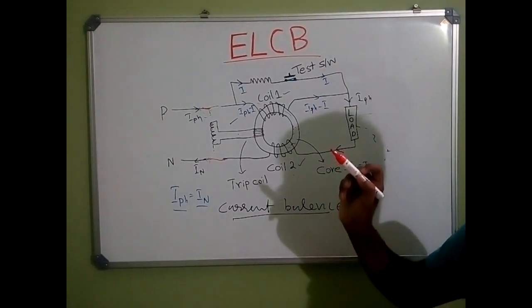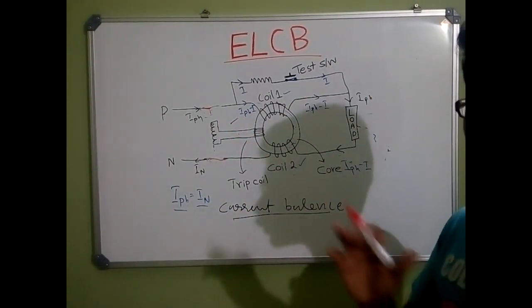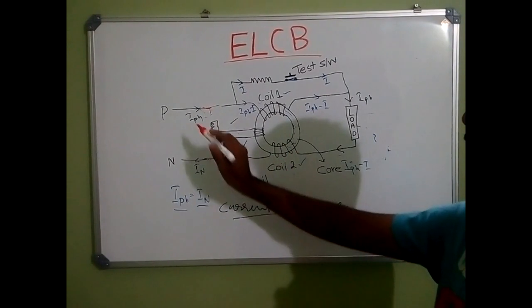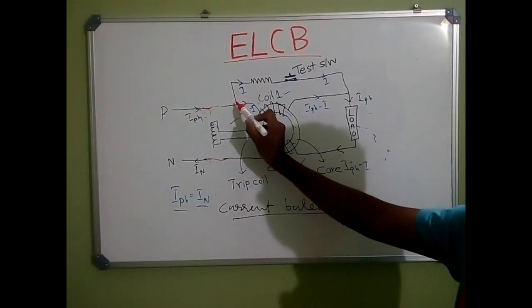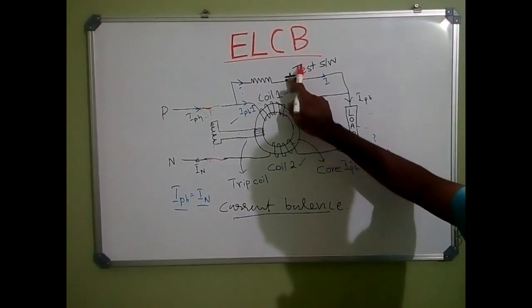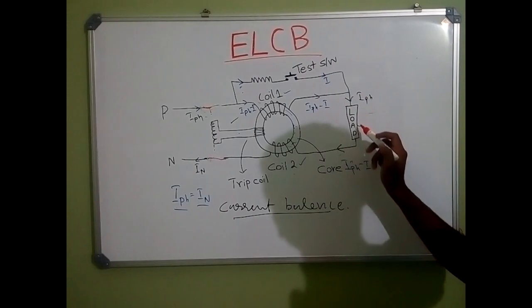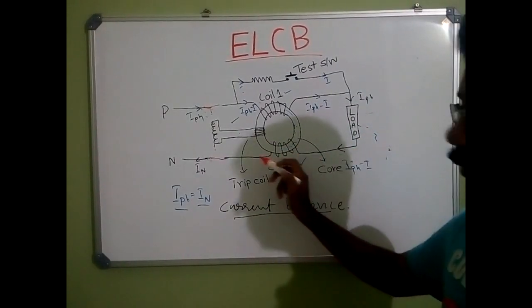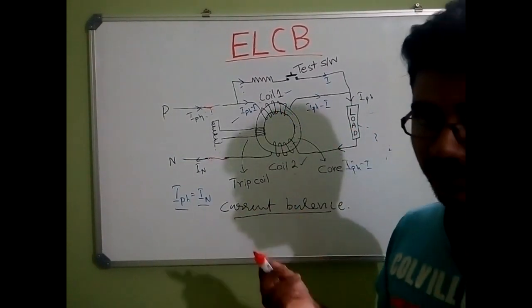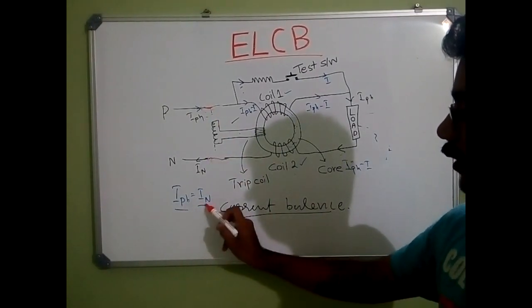Now we are going to look at how this ELCB works. The first condition we consider is the normal condition — that is, there is no leakage current. When there is no leakage current, this phase current flows through Coil 1, then through the load, then through Coil 2, and reaches the neutral. Since Coil 1, load, and Coil 2 are in series, I-phase and I-N are equal — that is, phase current and neutral current are equal.